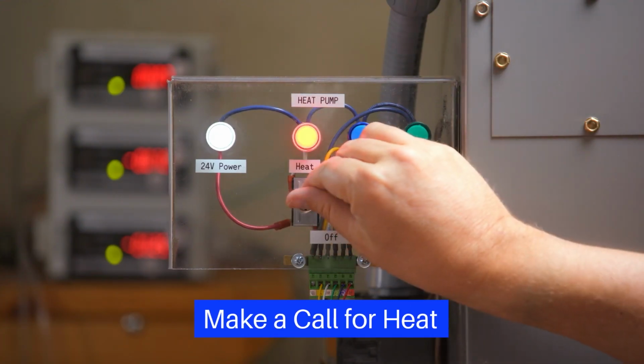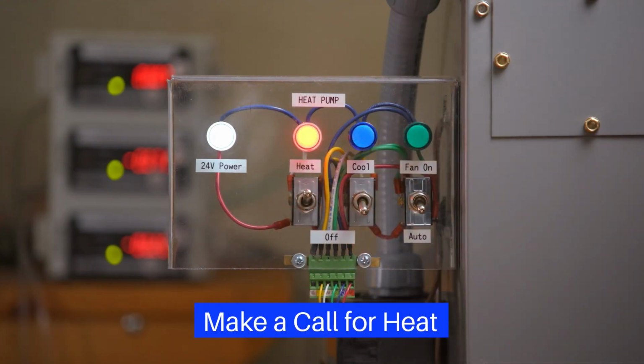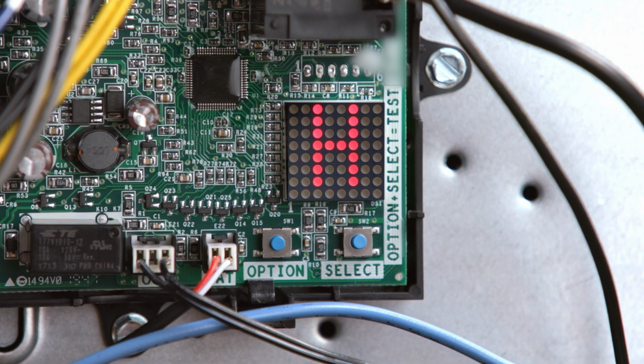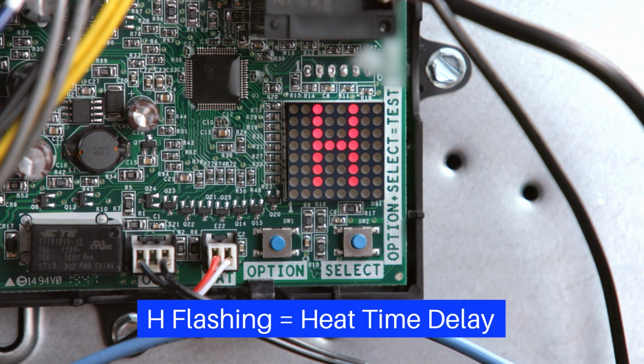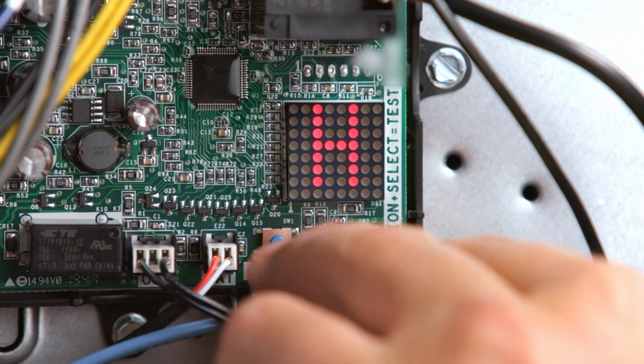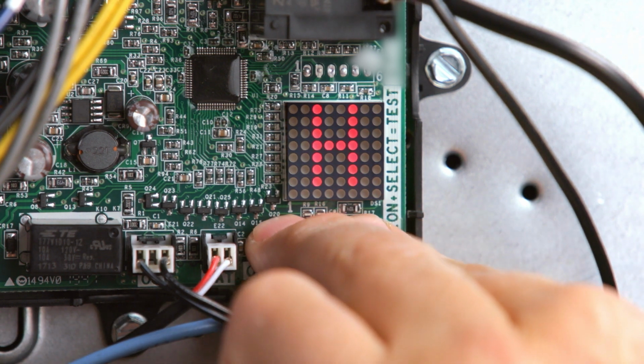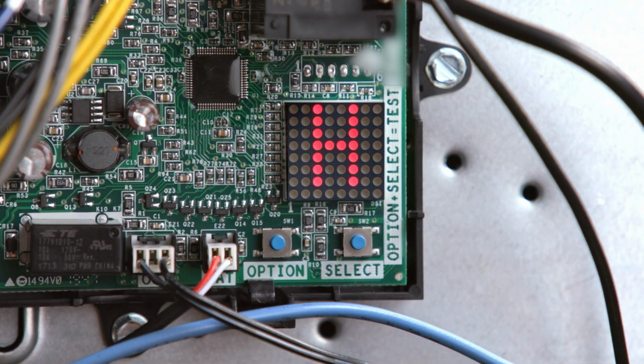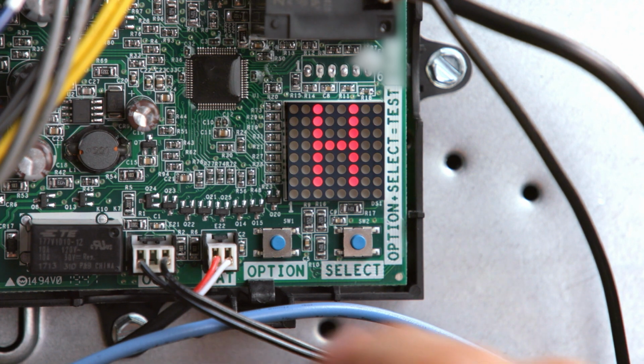To test the control, set the thermostat to call for heat. The control will display H for heating. Note that if the H is flashing, the compressor time delay is active. To bypass, press Option and Select for 1 second. The LED will briefly display a T, or wait for the delay to time out. With the heat pump running, the display will show an H.